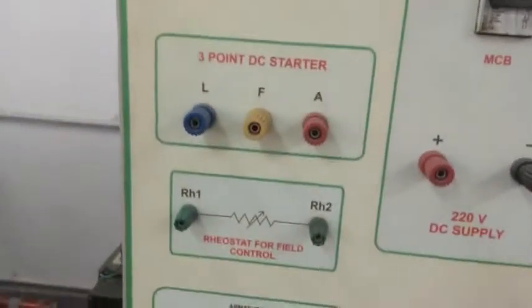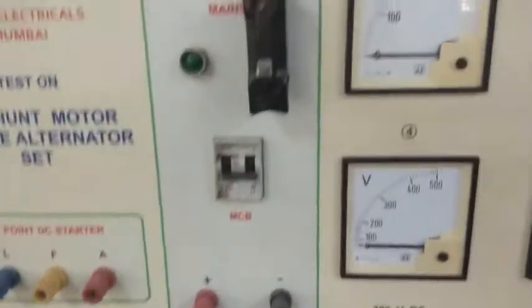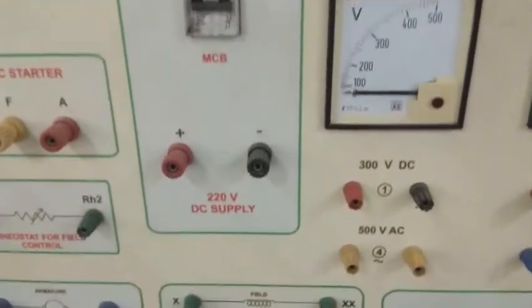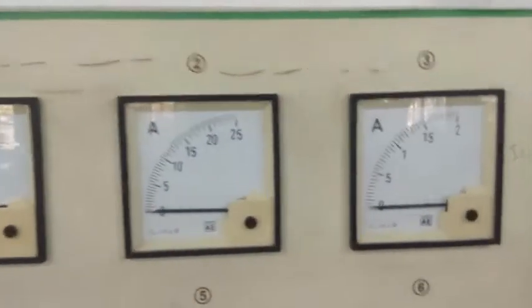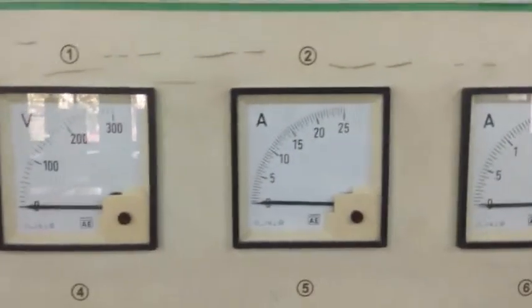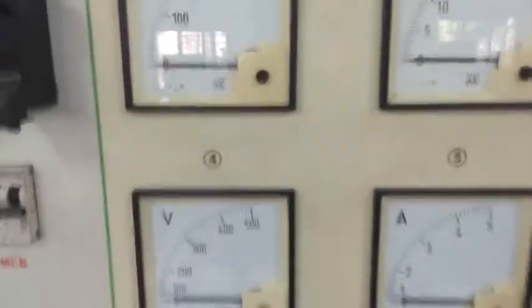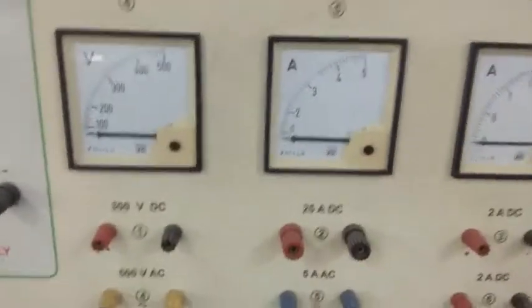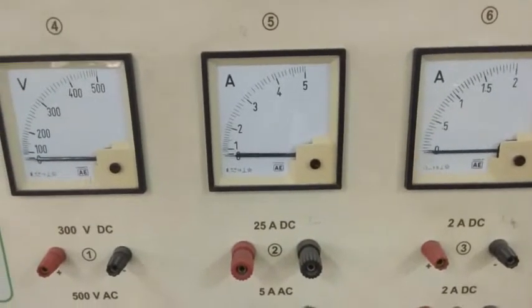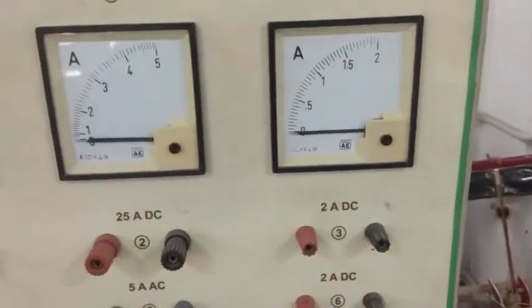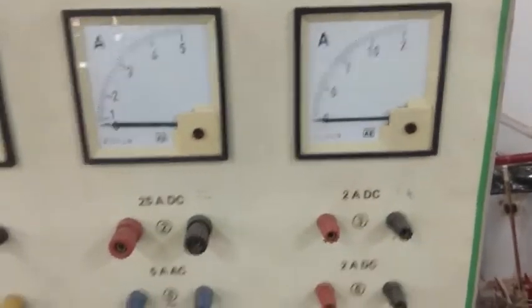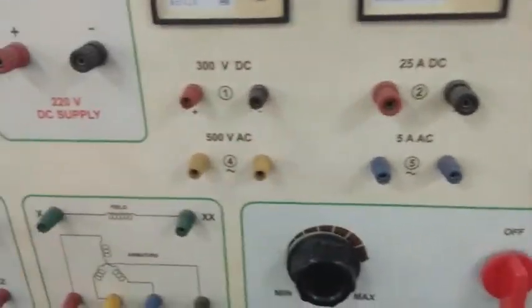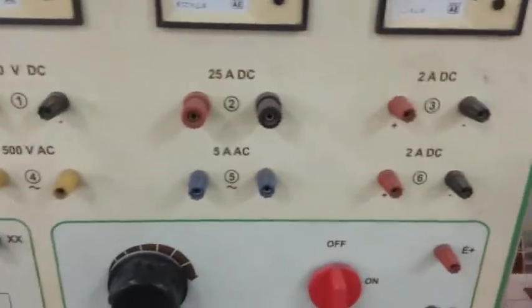Here there is a 3-point DC starter. Here there is a main switch for switching on the DC supply, 220 volt. Here there are the voltmeter and ammeters: a moving coil voltmeter and moving coil ammeter for the prime mover section. And below, here is a voltmeter for the alternator section, a moving iron voltmeter and moving iron ammeter, and one voltmeter from the DC excitation unit, and below is the terminal for the connection of all the meters.